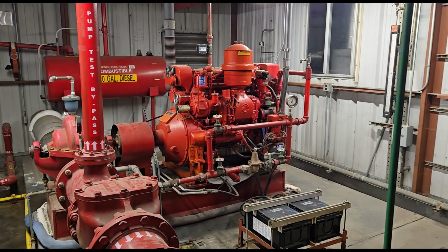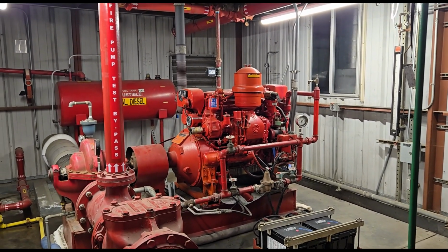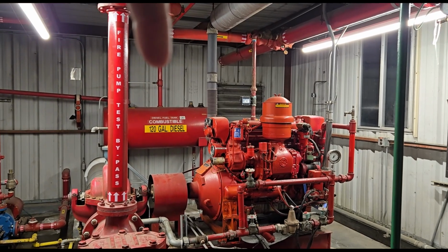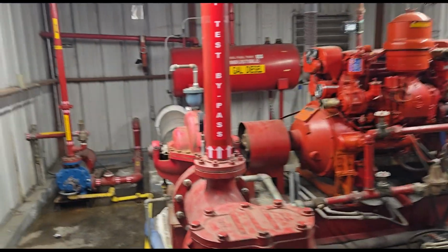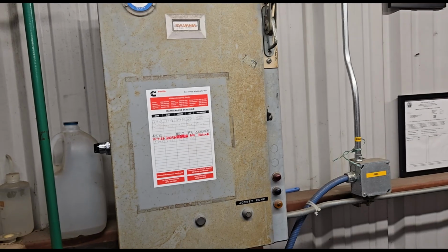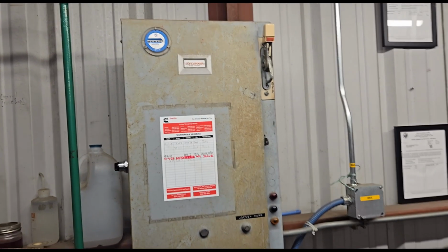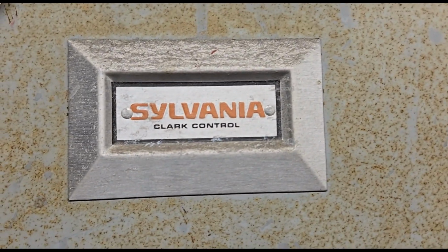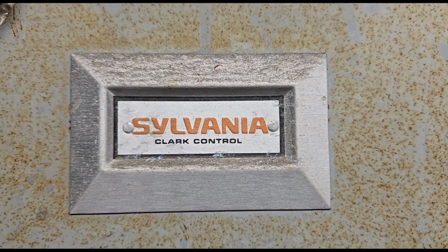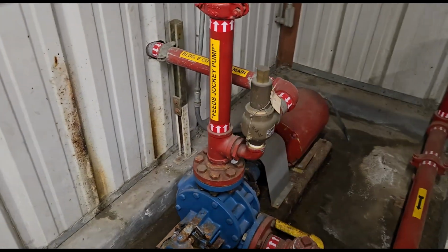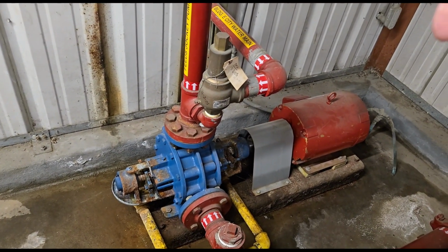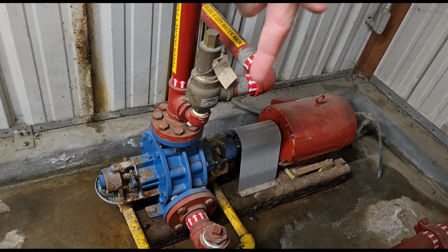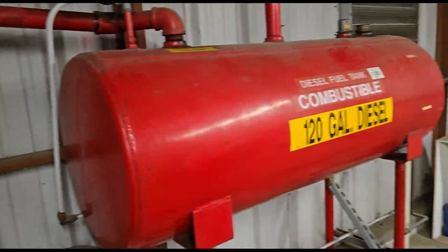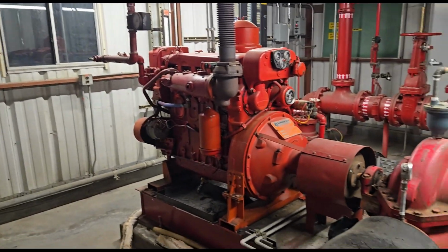So this is the fire pump here. You have your diesel tank, your fuel tank in the back. Then you have your fire pump here. So it looks like a horizontal pump. And then we have our jockey pump controller here. This is a Sylvania Clark control fire pump. And then we have our little jockey pump over here. So this is what all our flow testing is going to go through. There's this pump here. And again, this is the fire pump from the other side.